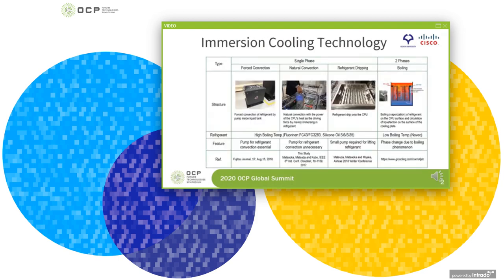The immersion technology, as we have reported on various occasions, exhibits high performance in cooling high heat servers such as HPCI. There are actually 4 ways to implement this technology, 3 of which are single-phase mode using only refrigerant, and the 4th is 2-phase mode using refrigerant and gas.